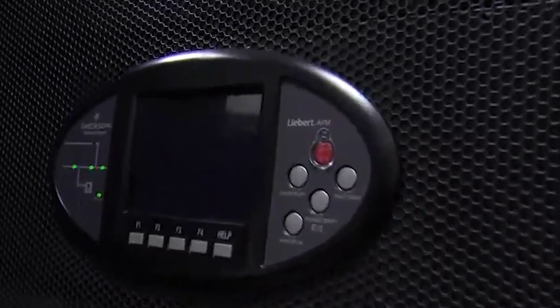And again, the same on this system. So we'll call this system A. We'll call this system B for now. So if I walked up and pushed that EPO button, both of these will go down. So again, this is your DC breaker. Will it go into bypass? It will not go to bypass. Your output and your input breakers will trip, and so everything supplied by these will go down. Correct. And that's an emergency power off situation where it's on fire or something's going on where you deem it an emergency and you want to take that responsibility of pushing that button.